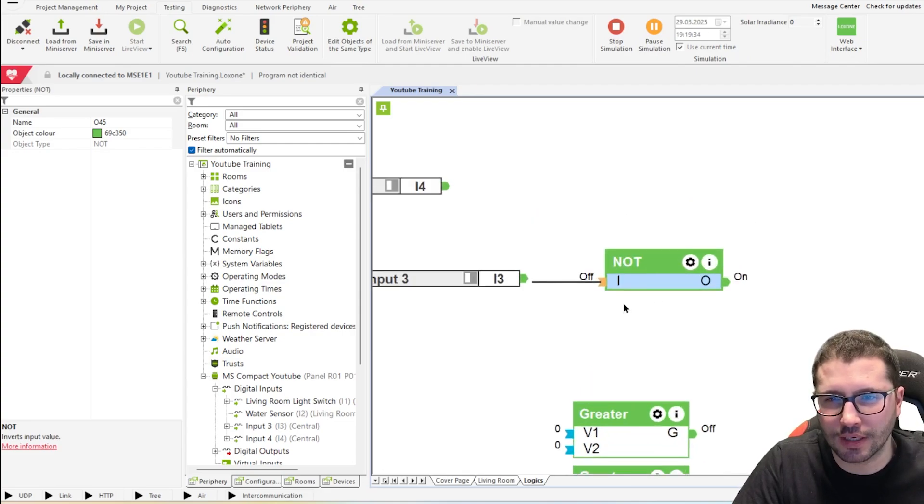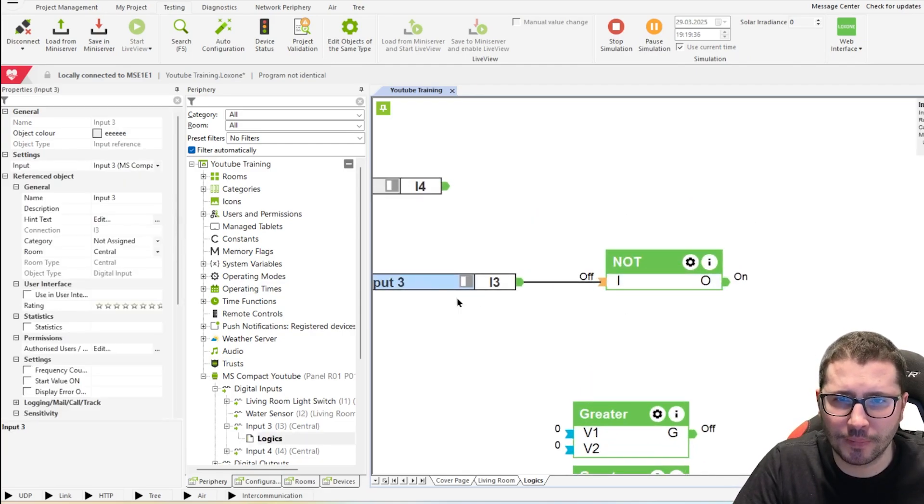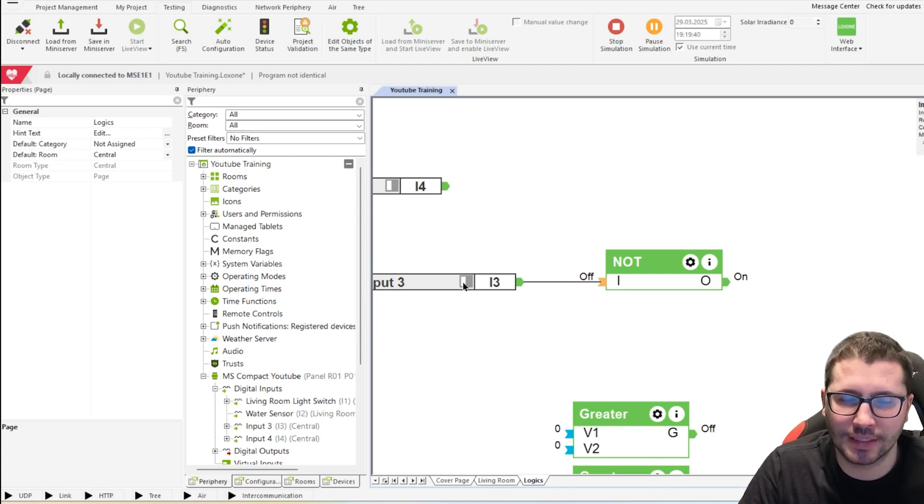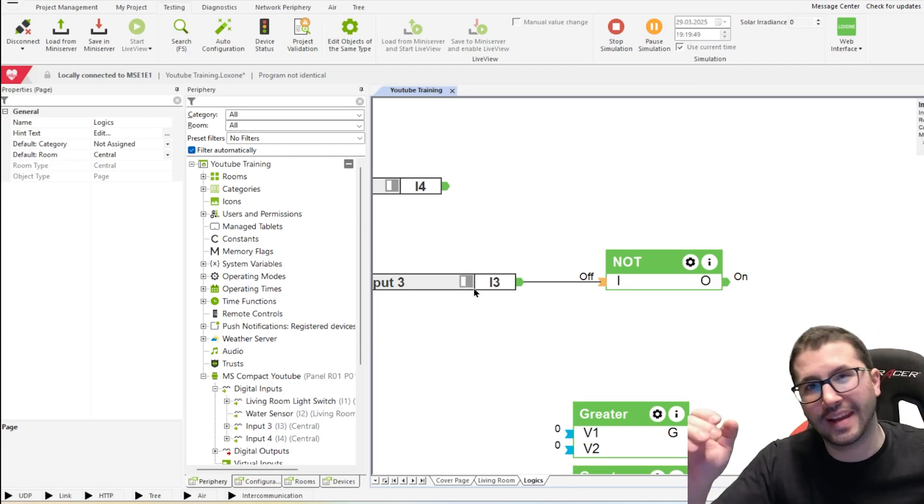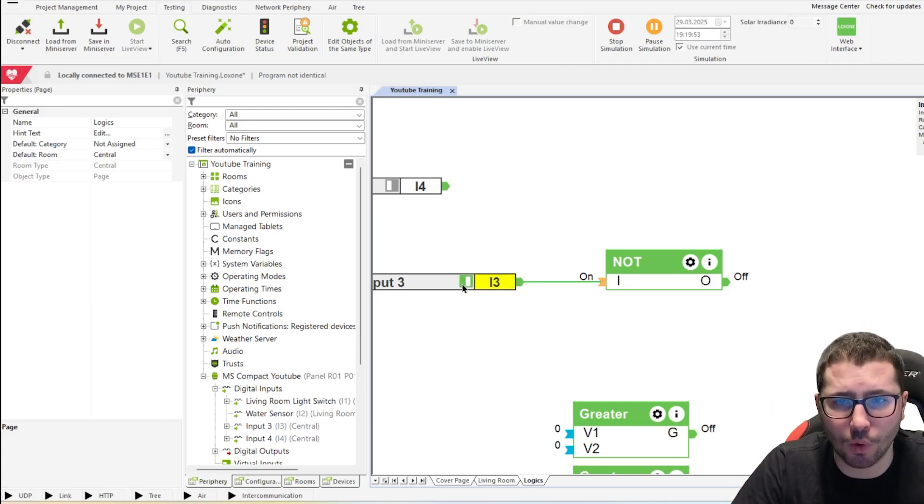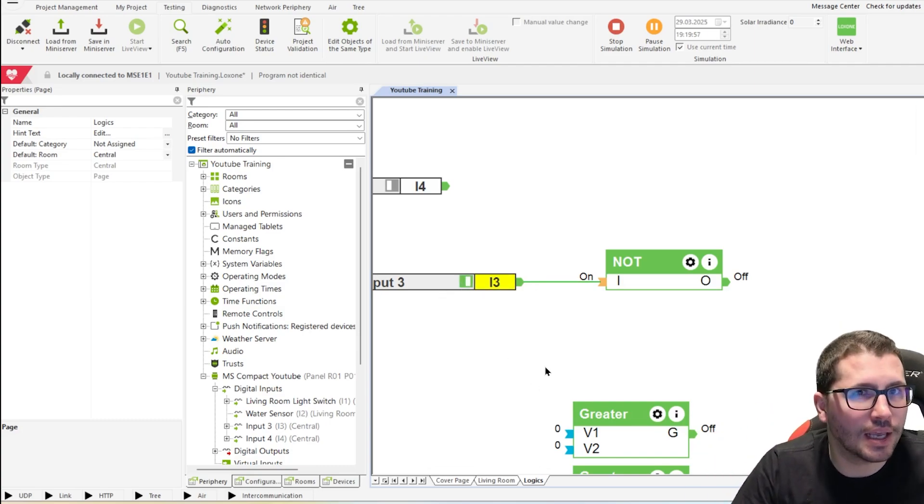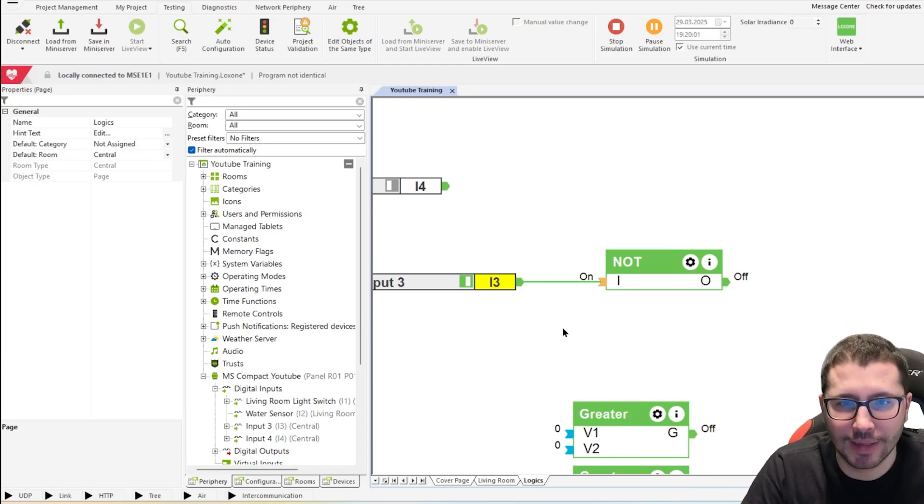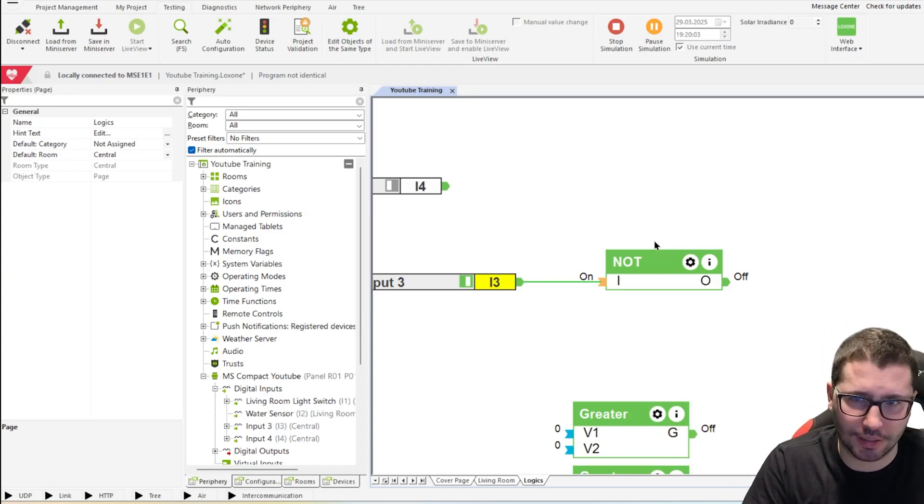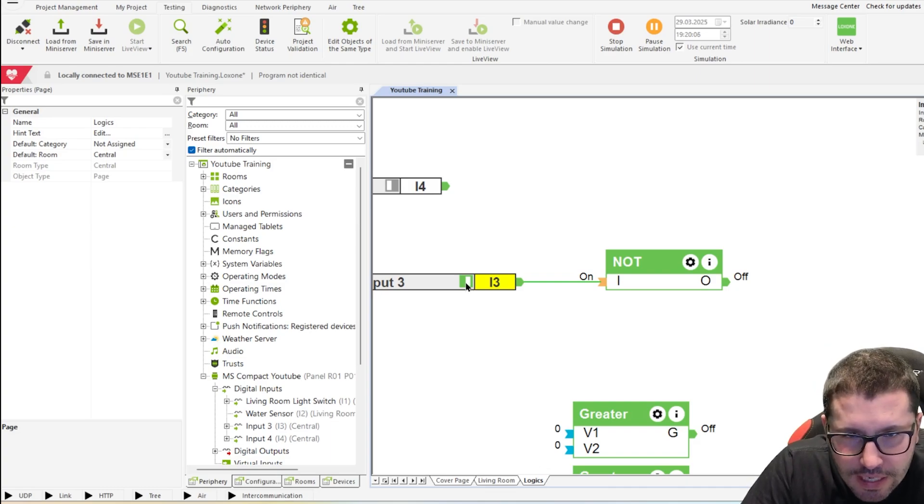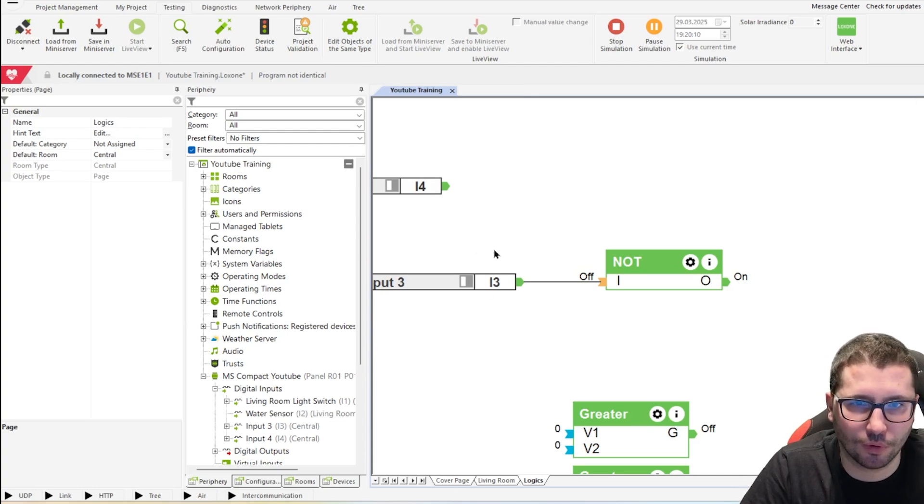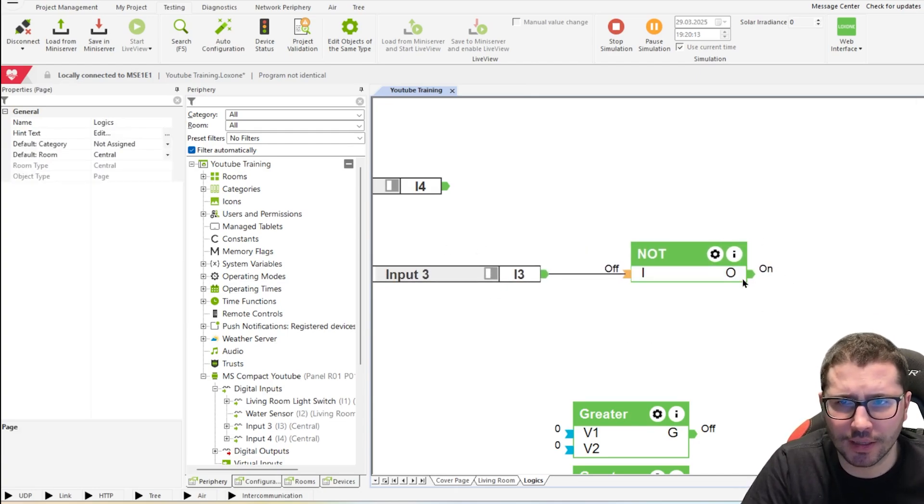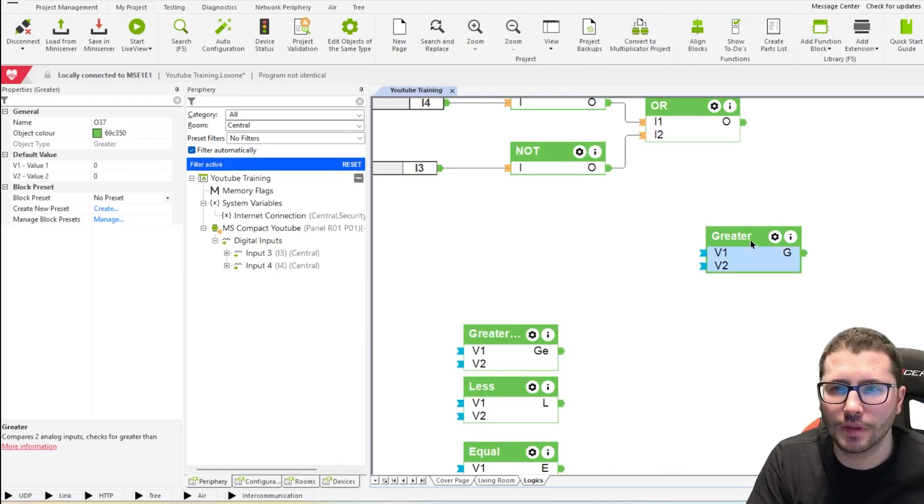So if the contact now gives us off and we would like to invert it like with a window contact for instance, when the window is closed, then the magnet pushes the contact so the signal goes through. But what if we would like to indicate that a window is open by turning on a light or something just as an example, then we would need to invert it. So if it's open physically, the state would be off. No signal. No 24 volt coming through. And then with the NOT, we invert it and then here we have the ON signal to do whatever we want with it.